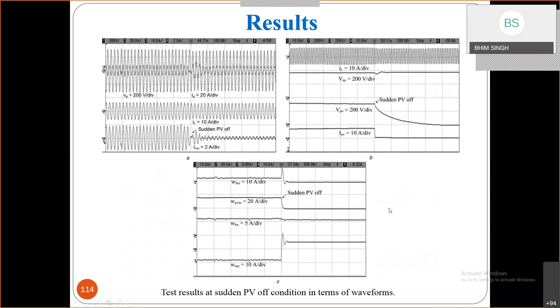We also extended this with a battery. In India we have relevant use for a battery: the grid should not experience the intermittency of solar generation, nor of the varying load, and the load should not experience the intermittency of the grid, which is very common in India since our grid is not always available. The local load should still get uninterruptible power. So we neither lose generation, nor does the grid experience abnormality, and whenever the grid is there we should be able to synchronize very smoothly.